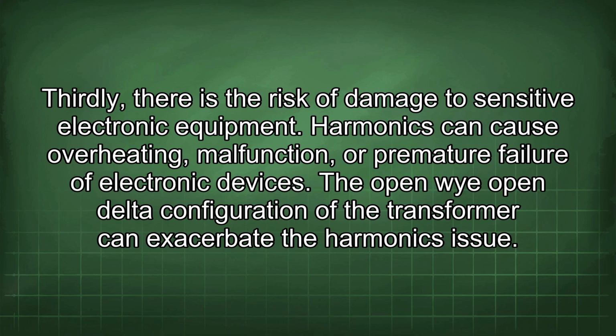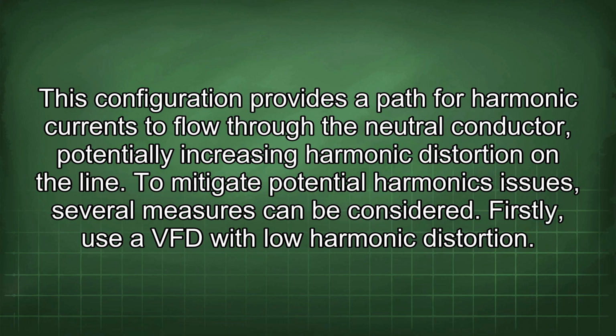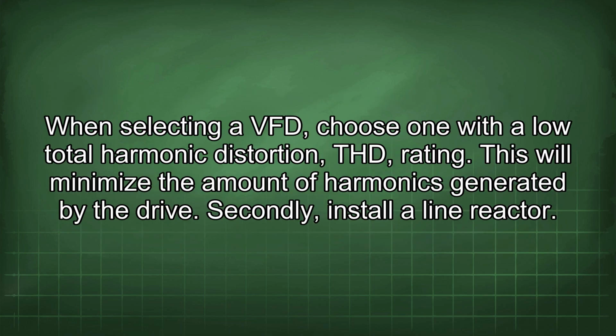The open Y-open delta configuration of the transformer can exacerbate the harmonics issue. This configuration provides a path for harmonic currents to flow through the neutral conductor, potentially increasing harmonic distortion on the line. To mitigate potential harmonics issues, several measures can be considered. Firstly, use a VFD with low harmonic distortion. When selecting a VFD, choose one with a low total harmonic distortion (THD) rating. This will minimize the amount of harmonics generated by the drive.